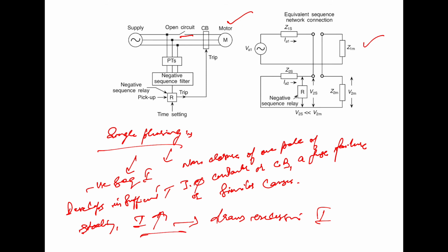Which leads to burnout unless the motor is tripped. So there is a thermal limit to the amount of negative sequence current that can be carried by the motor. The quantity that we have discussed, I2 squared T, represents the energy liberated as heat due to negative sequence current I2. I2 squared T equals 40 is conventionally used as the thermal capability of the motor to carry the negative sequence current, and this I2 squared T represents the energy liberated as heat due to the negative sequence currents I2.